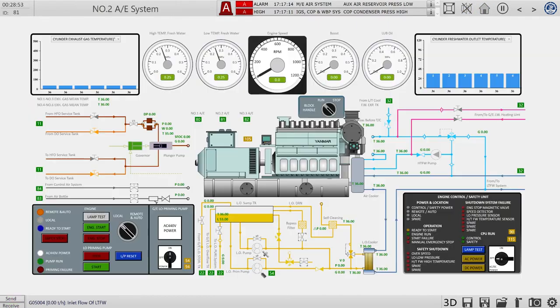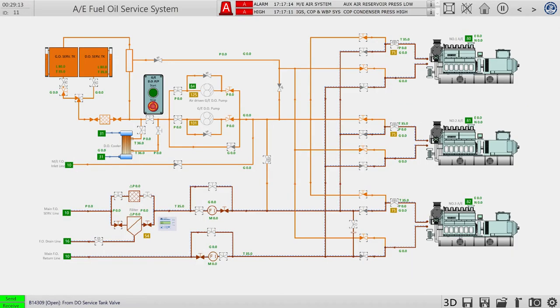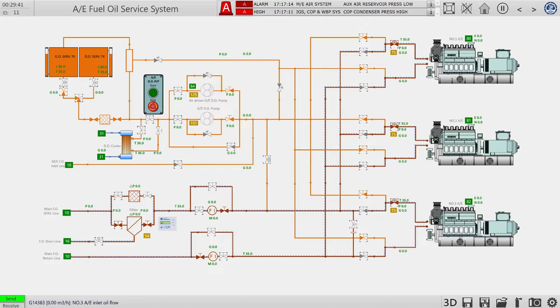Let's check number one locally — the fuel is received from the diesel oil tank. This is diesel generator number one: we have a diesel mixing tube, this is the return and this is the supply. This valve must be open because it is the inlet. I will change suction to the diesel oil service tank — the three-way valve will be changed.